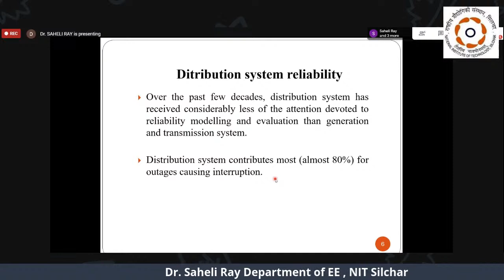In order to find the distribution system reliability, there are certain parameters like failure rate, outage time, annual outage duration. So actually, why are these parameters required? Basically, whenever we use the term reliability, it may seem sometimes qualitative, a sort of qualitative measurement. But unless we give some quantitative value, we cannot evaluate how reliable a system is. In order to get some quantitative measurement, it is required to have some parameters which will define the system's reliability as a whole.